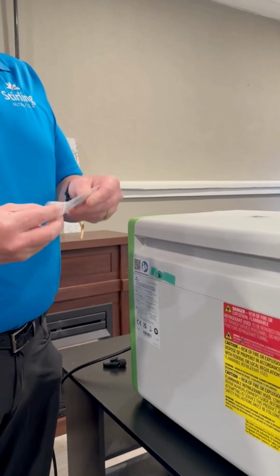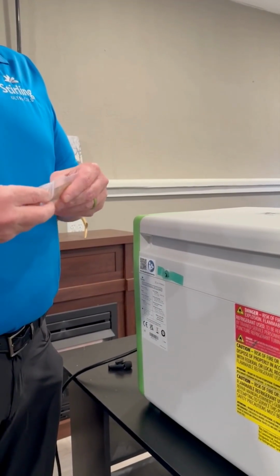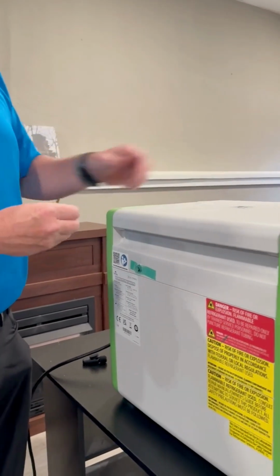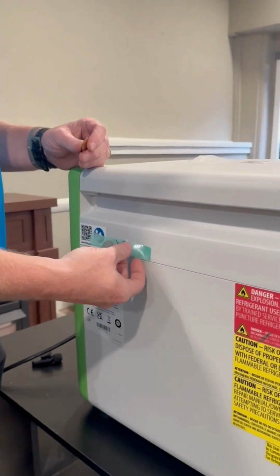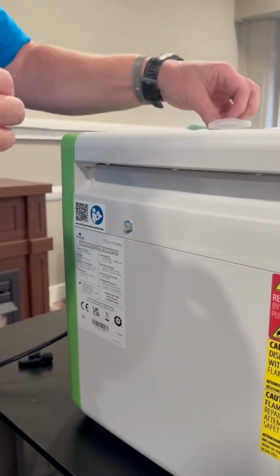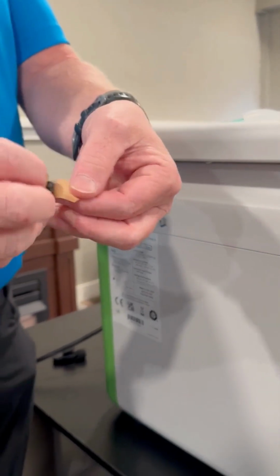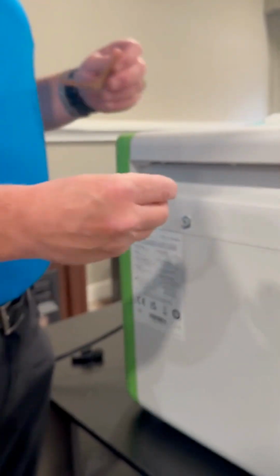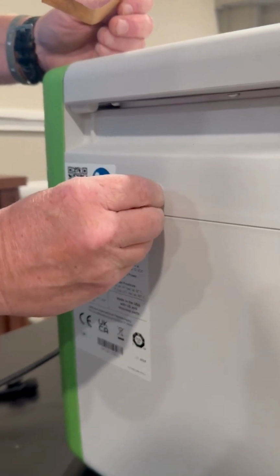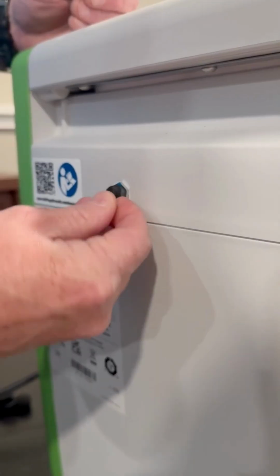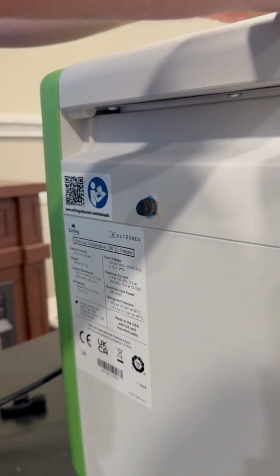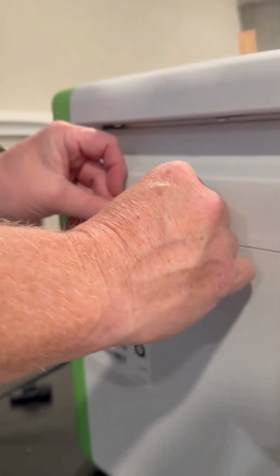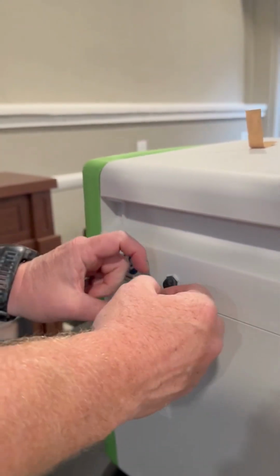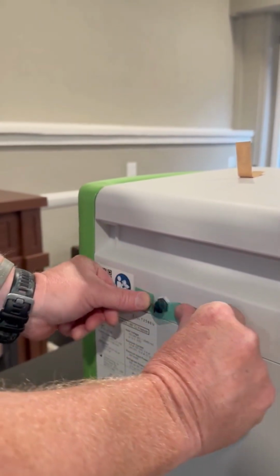This freezer will come with our rubber port stopper product. This is for if you are not running a temperature monitoring probe in the side of the unit. You will see that there is always a piece of tape over the hole. What we recommend is that you take out the port stopper, the rubber pieces, and it's just like silly putty. You just stick it in the hole, make sure that hole is covered, and then you can use that tape or any other tape around your office or lab and put that back on, and that will seal up that port hole.